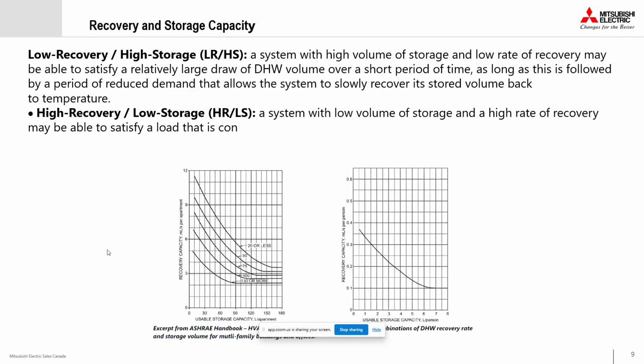As long as this is followed by a period of reduced demand that allows the system to slowly recover its stored volume back to temperature. So you have a high demand for a short period of time. Instead of sizing your equipment for that high demand, you can size the equipment for a little lesser capacity and then compensate for that peak with a supply from storage.